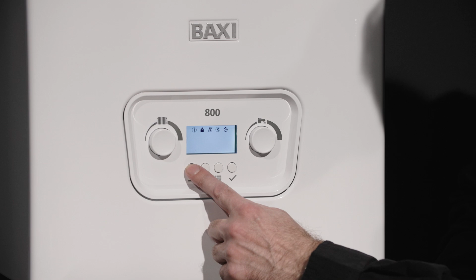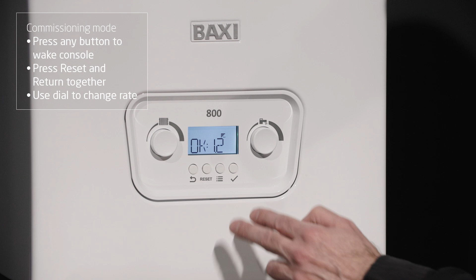So now I'm going to run through how to get into commissioning mode, or commonly known as chimney sweep mode. And it's really simple. All I have to do is press the reset and the return button at the same time. One note, if the display isn't on, just press any button to wake it up. Then I press and hold these 2 buttons for about 5 seconds. And what you can see there, I get a capital L. That's low rate. The boiler will fire on low rate.